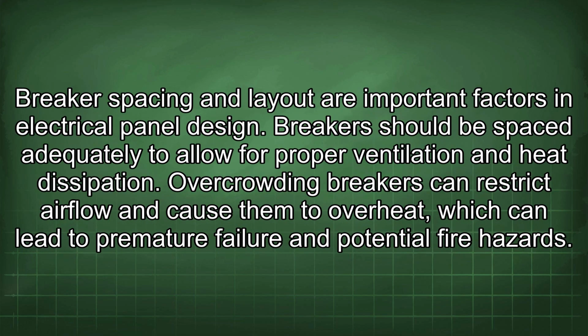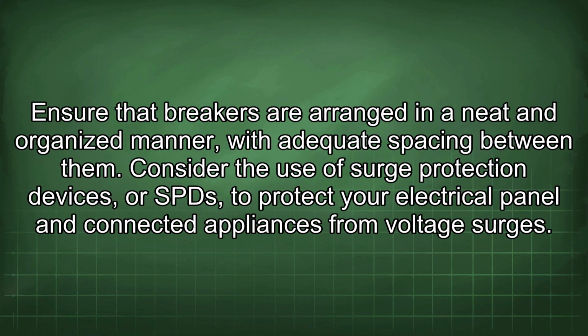Breaker spacing and layout are important factors in electrical panel design. Breakers should be spaced adequately to allow for proper ventilation and heat dissipation. Overcrowding breakers can restrict airflow and cause them to overheat, which can lead to premature failure and potential fire hazards. Ensure that breakers are arranged in a neat and organized manner, with adequate spacing between them.